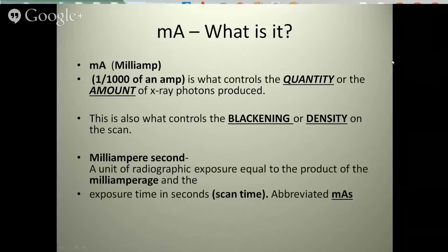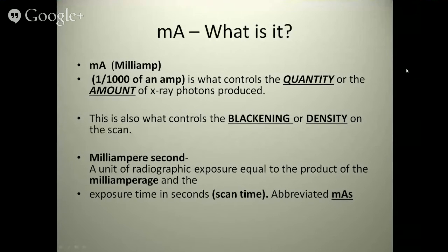MA controls the quantity or amount of X-ray photons produced, basically radiation, and it controls the blackening or density on the scan. Since that can change depending upon the milliamps that you have set on your machine, that might be one reason why when you try to read Hounsfield units in the software, all the software companies say it's not an exact figure, just an idea of the bone quality.